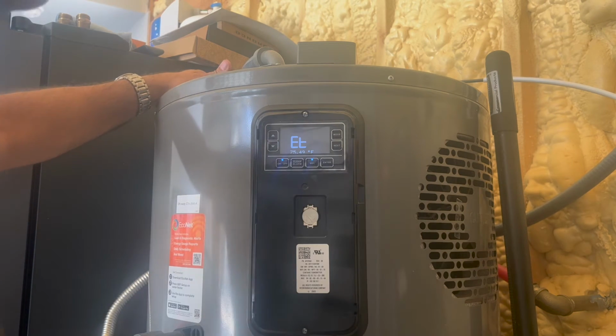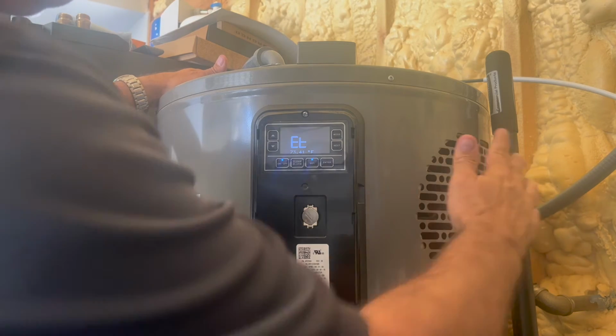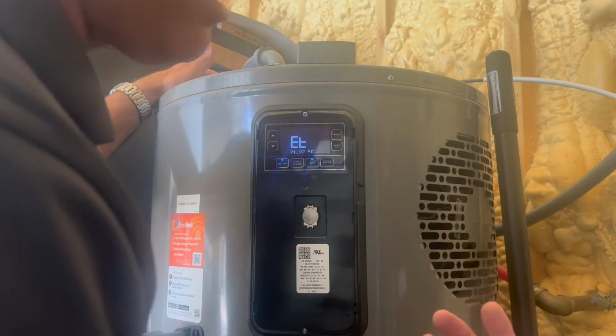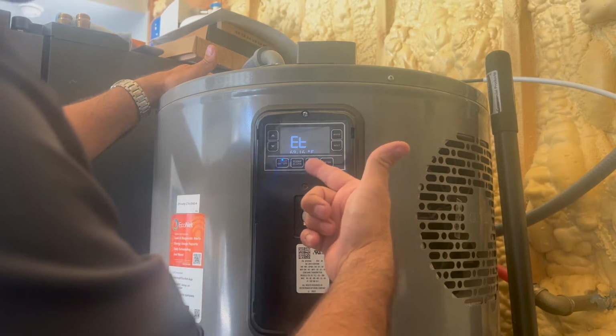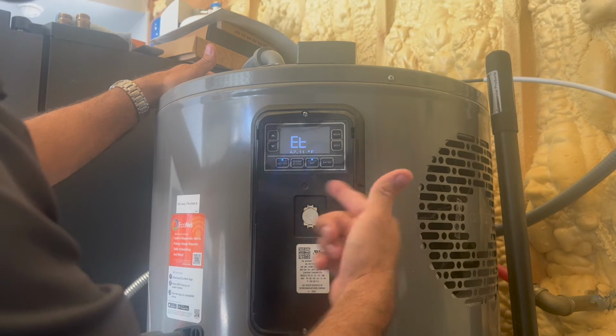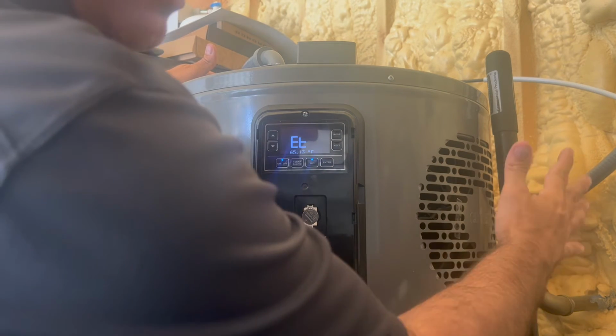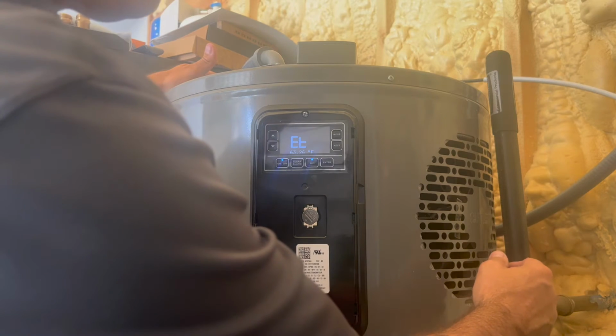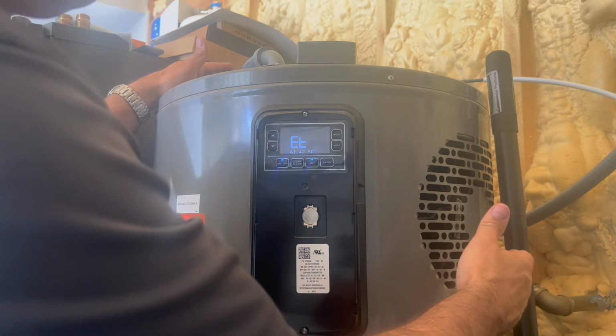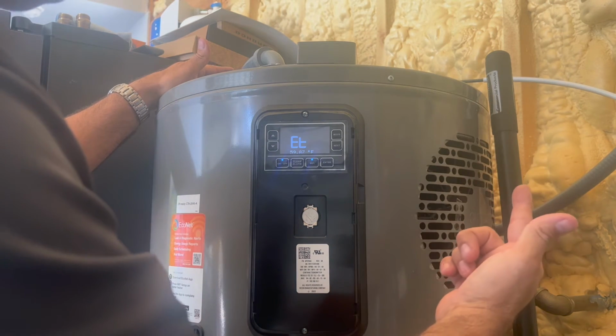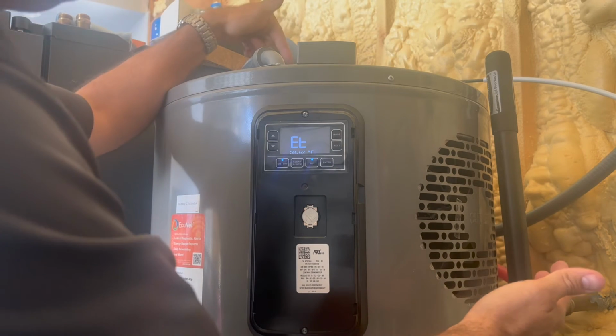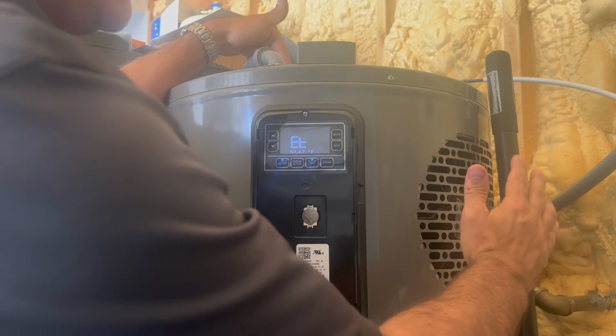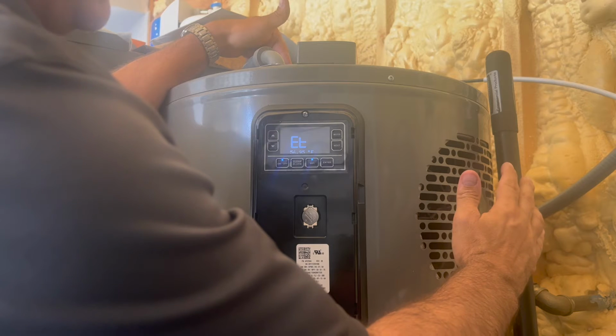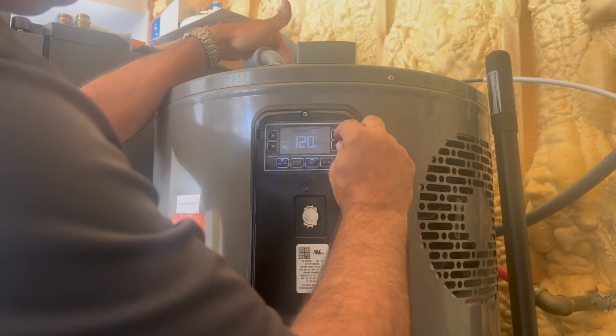All right, now we're getting a good test here. We're seeing that the evaporator temp is going down. We're 90 degrees in here. This evaporator temperature is showing to be in the 60s now. That air is nice and cold. This is telling me what? That the ambient temperature is 90. The evaporator is removing heat from the air. Oh, well, I lost my test.